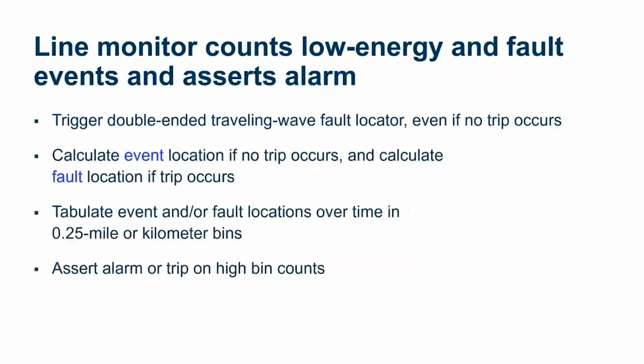But the next thing I'm going to talk about is a line monitor. This also uses a double-ended traveling wave technology, and this calculates an event if no trip occurs. What we found is that we were seeing traveling waves launched before faults occur, and looking at those traveling waves that were launched before faults occurred, we could see that those traveling waves pinpointed where the actual fault occurred. So it was giving us kind of a precursor of what was going on in the system. So we're going to be listening for these non-fault traveling waves. Then we're going to split up our line into quarter-mile or quarter-kilometer bins, and we're going to count how many traveling wave events we're getting in each one of these bins.